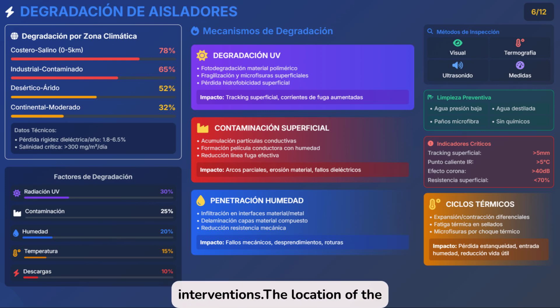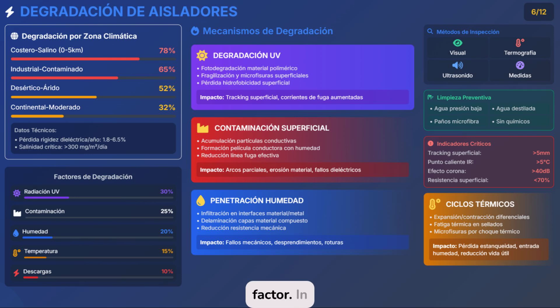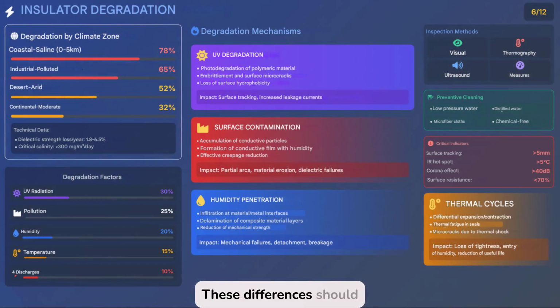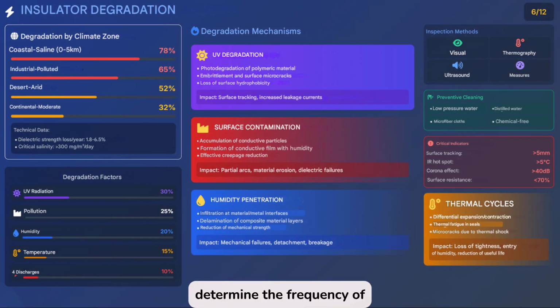The location of the substation is a decisive factor. In coastal saline areas, degradation reaches 78% due to salinity and humidity, while in industrial areas, it is 65%. In desert climates, it reaches 52%, and in moderate environments, it drops to 32%. These differences should determine the frequency of inspections and cleaning strategies. As not all locations face the same risks.